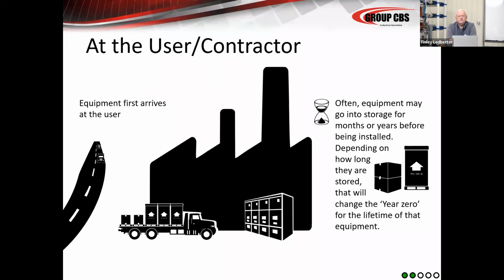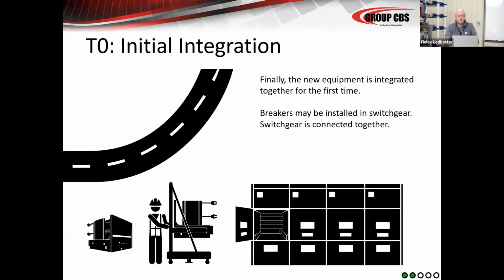So look very closely at what your actual warranty is, because you can set it in a warehouse with no heat on it, outlive the warranty before you install it, and do substantial damage to the equipment, degrade it substantially if it's not handled correctly and stored correctly. So always watch that and try to figure out where year 0 is. Where does your warranty actually start? Is it going to start in 5 years and 3 years and 1 year after installation? You need to know that from the plant level.